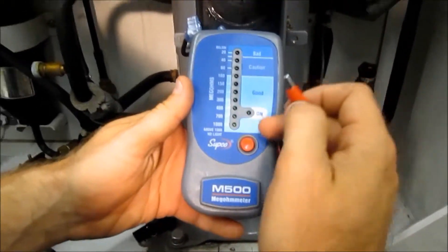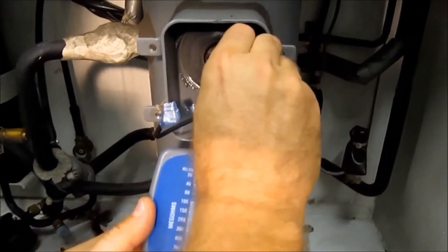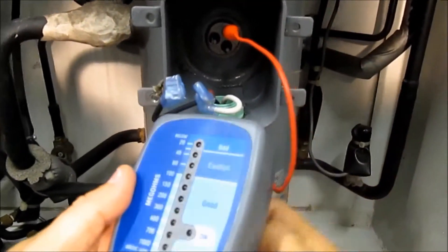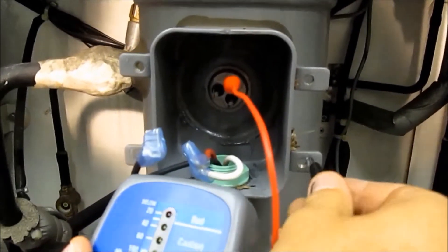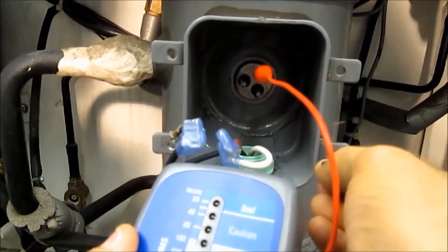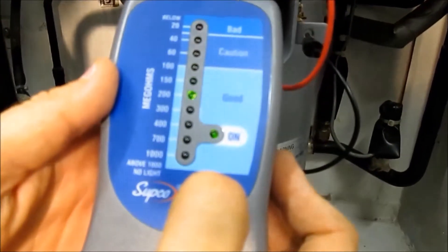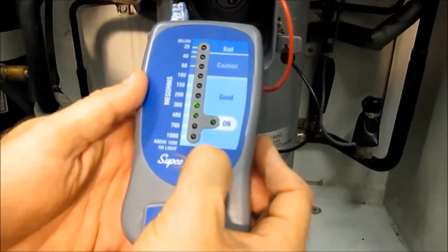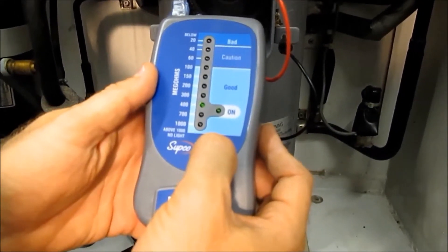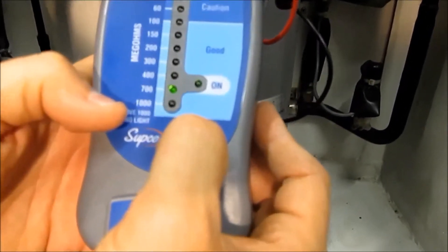Now we're going to check the compressor with a megger. So we go one lead here, and then we put the ground on a ground spot. Then we hold the button, and we've got to hold it there. This one is checking out good. You've got to hold it for a little bit.